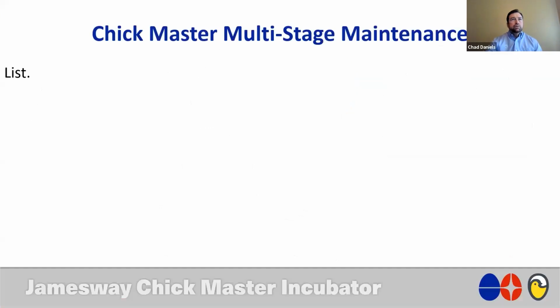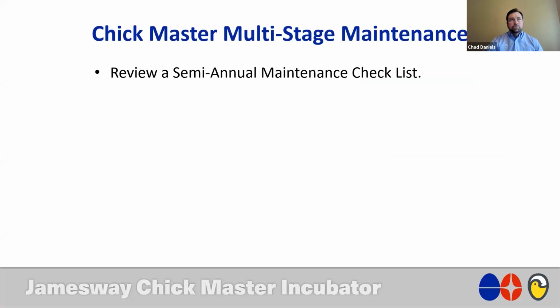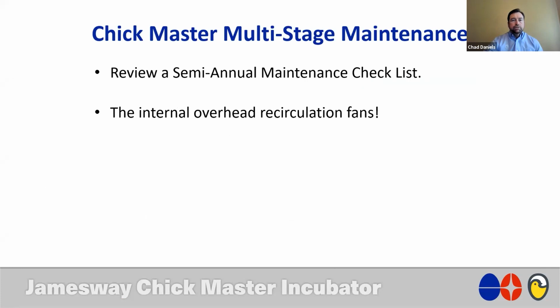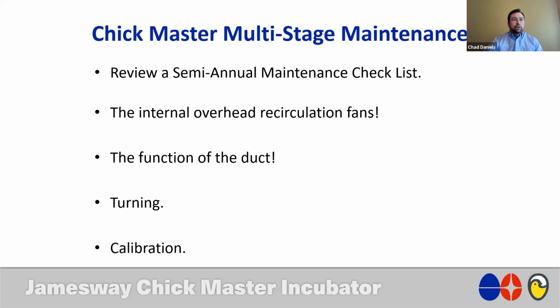So to begin with, we will review what I use as a semi-annual maintenance checklist. I've designed this one specifically for the classic multi-stage incubator, and we'll go through that in detail. We're also going to discuss the heart of the machine, which is the internal overhead recirculation fans, and as far as maintenance and making sure that those function properly. The function of the duct, if you are in a situation where you have some older machines and you still utilize the duct system, we want to make sure we cover that. Turning, which is very critical, and then also calibration. So hopefully we'll answer a lot of questions in regards to these specific topics.